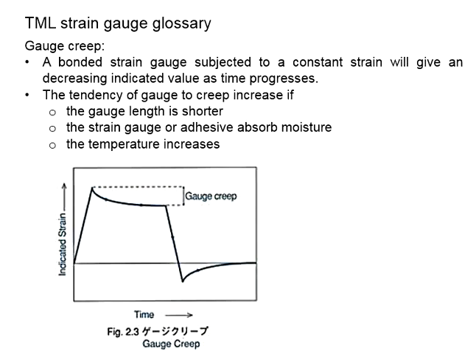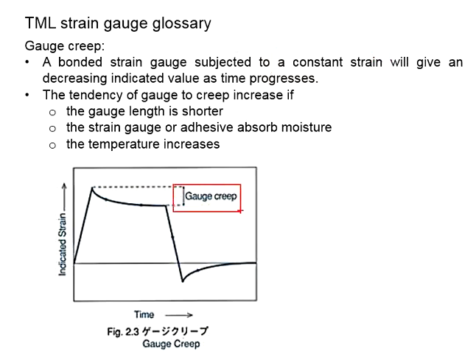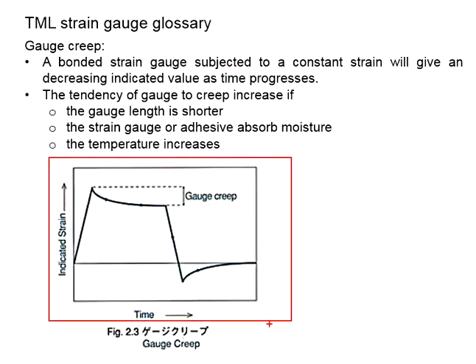Now let us proceed with the other terminologies related to strain gauge. We have gauge creep. When a strain gauge is bonded to a test specimen and it is subjected to a constant strain, gauge creep can happen. There will be a decreasing indicated value as the time progresses. This phenomenon is represented by the figure here.